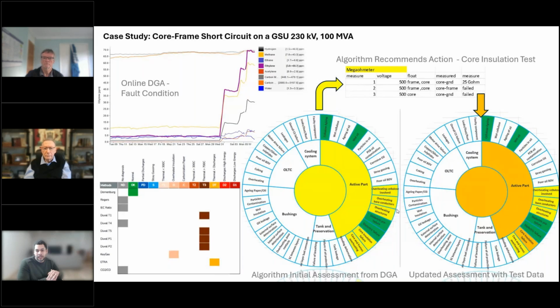You can see some of the suggested potential faults are overheated cellulose, overheated bare conductors, overheating structures, and core insulation failure. Those identifications indicate to the asset manager: I should attempt these tests on the outage. One of the recommended actions here is the core insulation test.